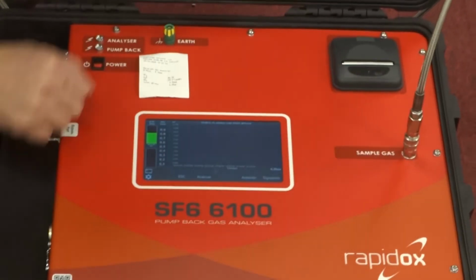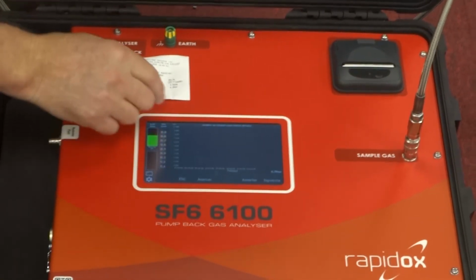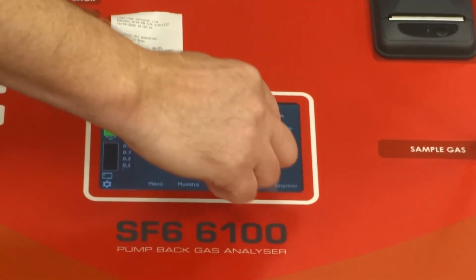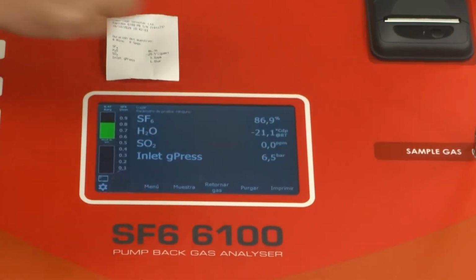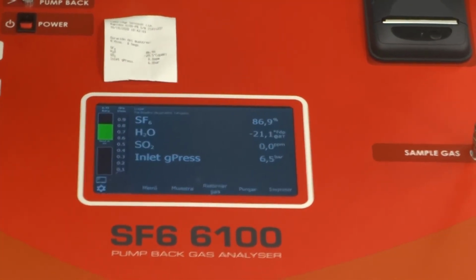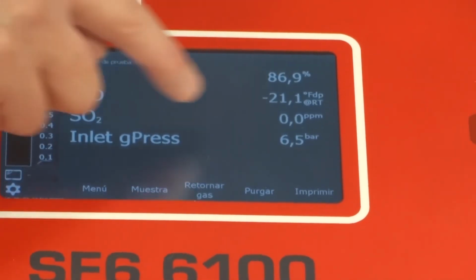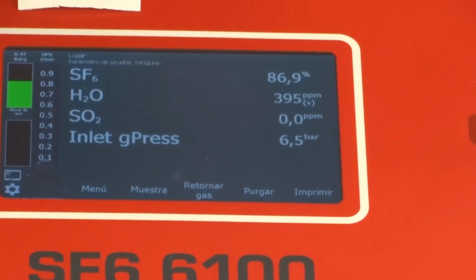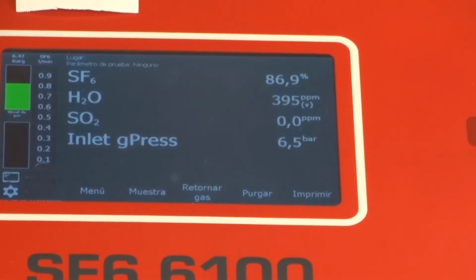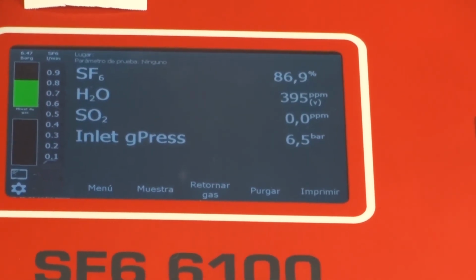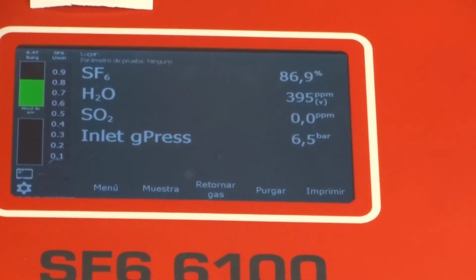Finally, here's the gas pressure. You can see actually, if you zoom in, the pressure is very slightly dropping because the gas is being removed from the pressurized cylinder. Okay. Now, on the results side of things, if you tap your finger on the units of dew point, you'll see that's changed to Fahrenheit dew point. If I press again, it will display ppmV, parts per million by volume. So 395 parts per million by volume.